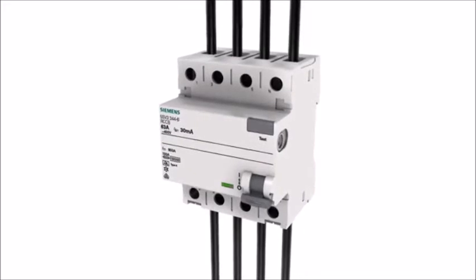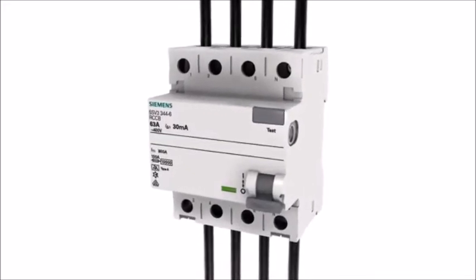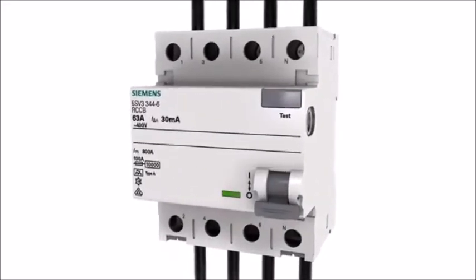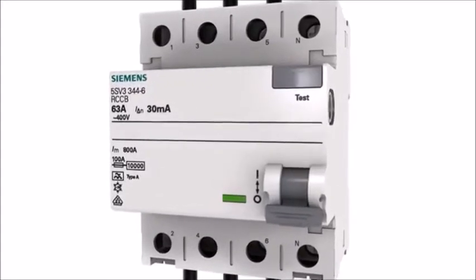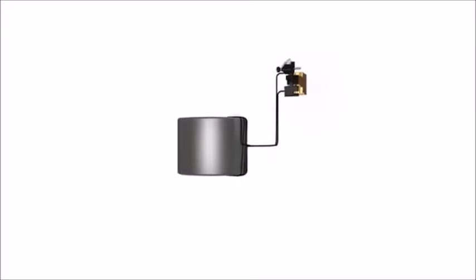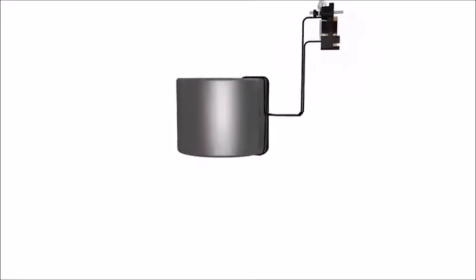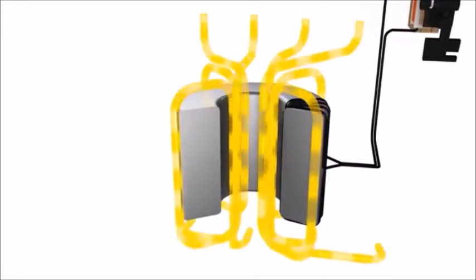Residual current protective devices offer numerous comfortable functions. This animation gets right to the heart of a residual current operated circuit breaker. The current flows through the summation current transformer in the RCCB. In a fault-free system, the magnetic fields generated by the live conductors cancel each other out. Thus, there is no residual magnetic field to induce a voltage on the transformer's secondary winding.